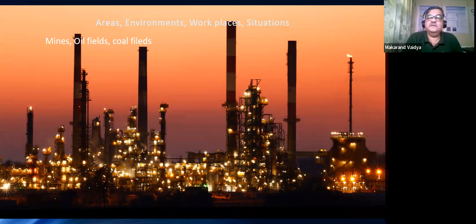Followed by the oil fields. In oil fields, actually this flame and explosion proof concept is not the purview of oil or coal only. It is actually about gas, dust, and fibers. But the oil fields usually have natural gas first and then oil follows. Coal also has methane always present in the coal fields. So mines actually started this area of concern.